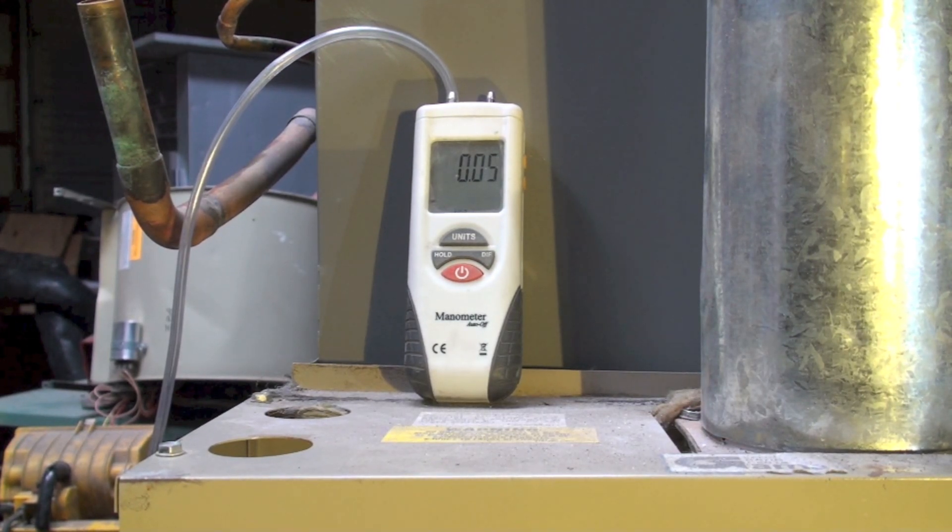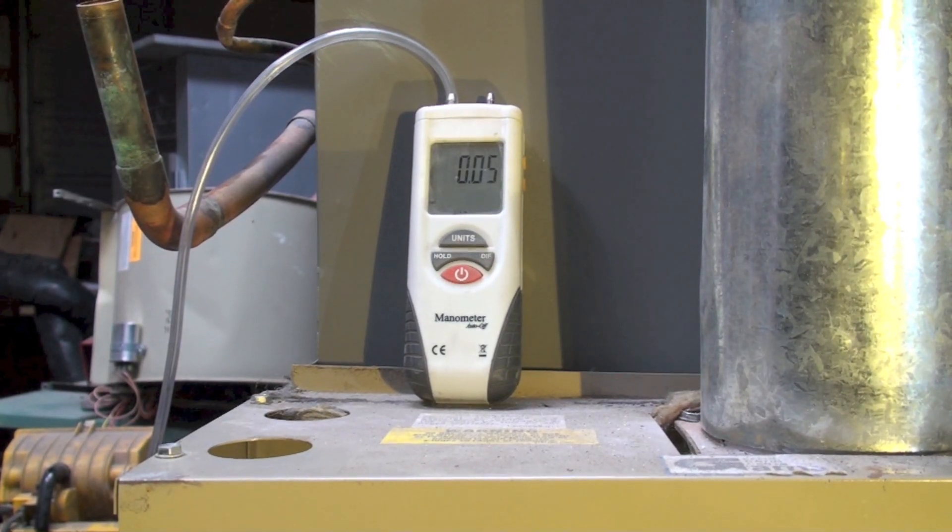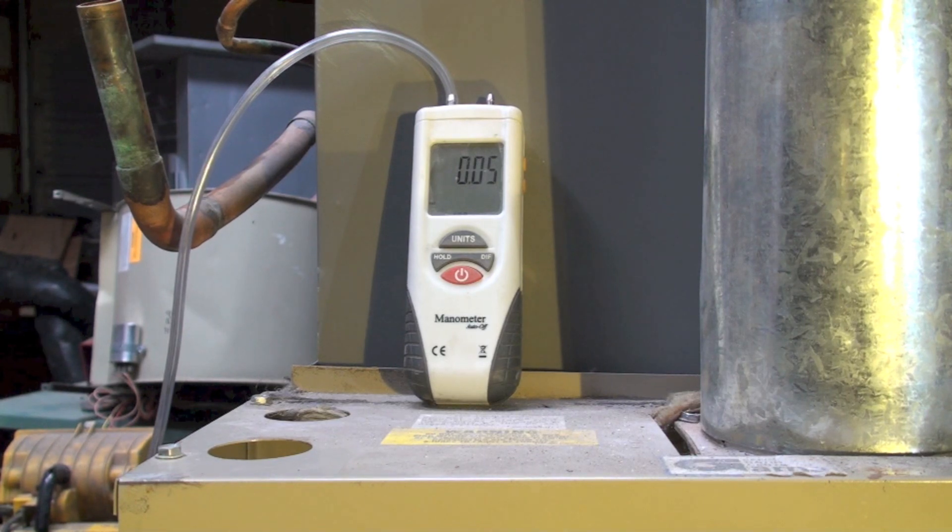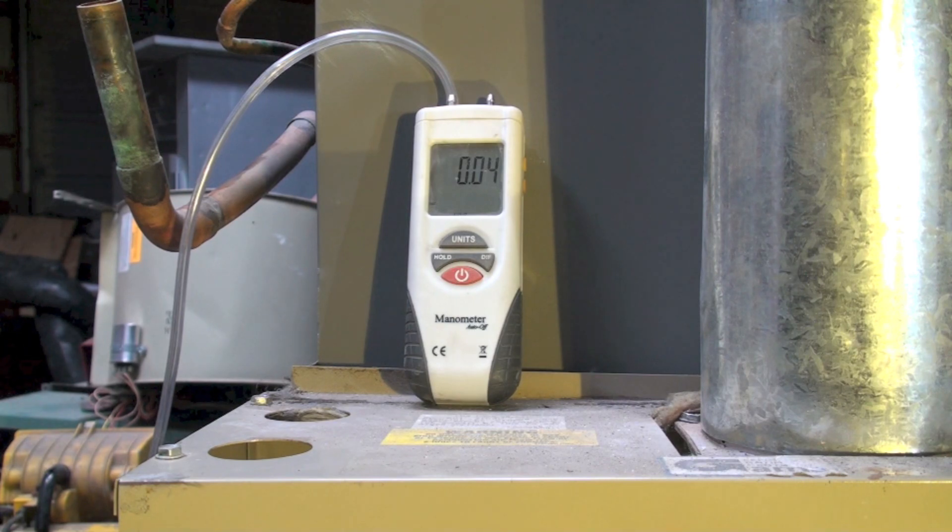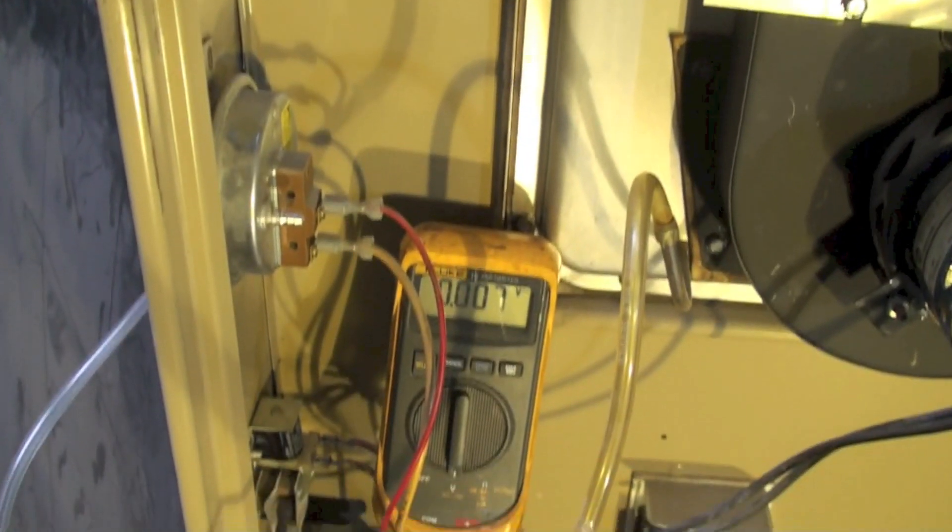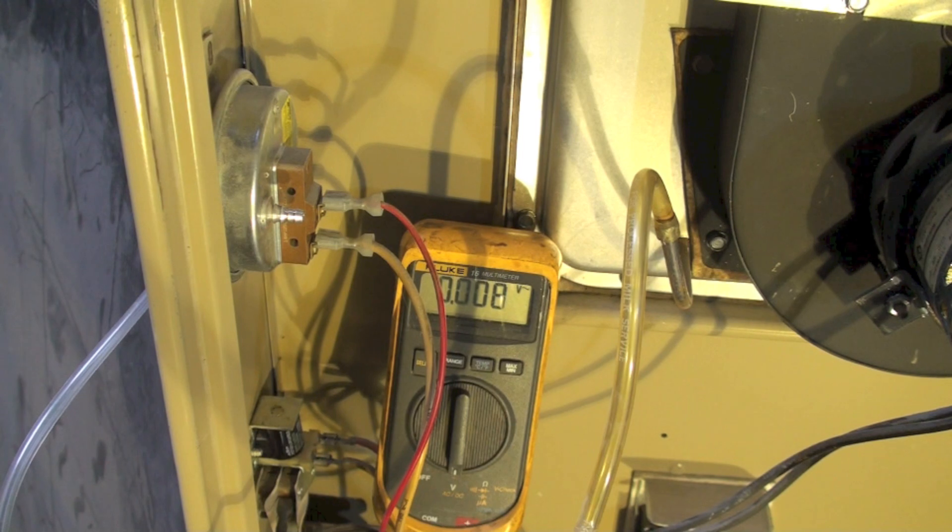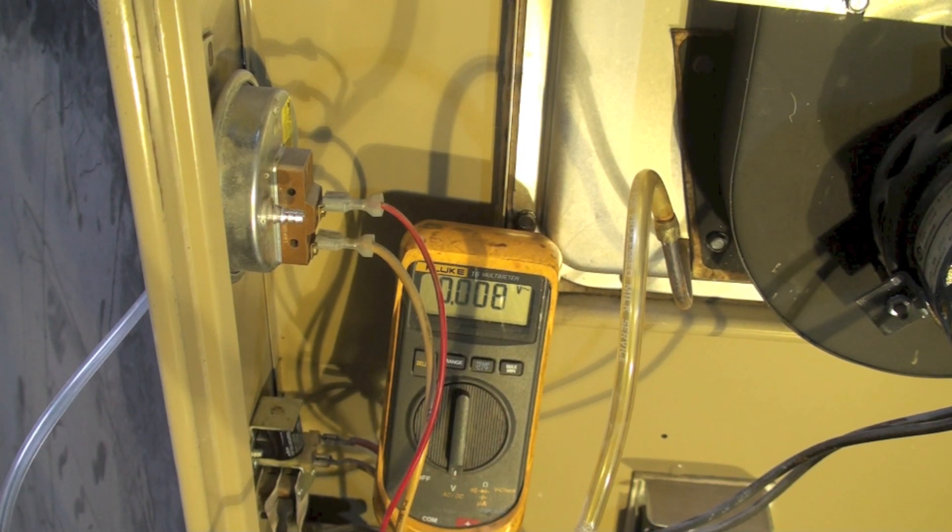Does that mean the pressure switch is bad? No, it means I got a blockage. Obviously the inducer is running. Could have a vent blockage, I could have a blockage here in the sensing tube, something like that.